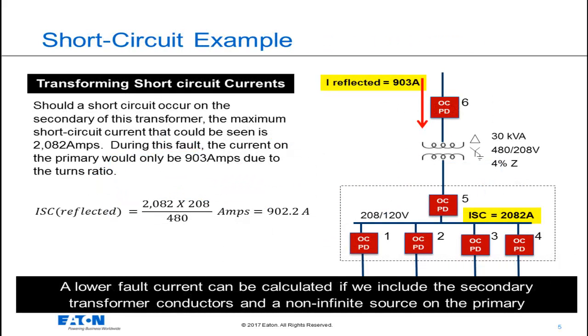Here's another example that addresses the transformation of short circuit currents when the short circuit is on the secondary of the transformer. For this 480 to 208 volt transformer, should a fault occur on the secondary, the maximum short circuit current that could be seen on the secondary is 2082 amps. Using our equation to reflect this current to the primary shows us that the primary current would only be 903 amps.